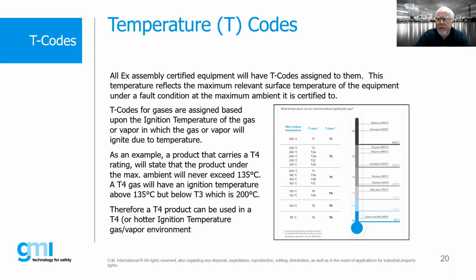So what does that mean from a product standpoint? A product that has a T6 rating means that that product, under its highest ambient in which it's suitable, will never exceed 85 degrees C under normal or fault conditions on its relevant surface, meaning that in effect, we can take a T6 product and put it into a T6 area. The same thing holds true if we have a T6 product. We can use that product in every area based upon its T code.